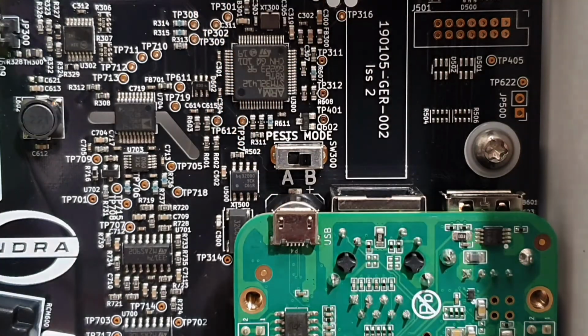The really clever thing about this charger is that you can set it to meet the requirements of all of these indents as long as it's on the correct setting. If you're using it to comply with indent 4, then you'll need to set the switch to mode B. Personally, if I was installing this charger, I'd always go for the reference earth electrode option wherever possible, but in situations where it may not be, I'd then fall back on the indent 4 solution.